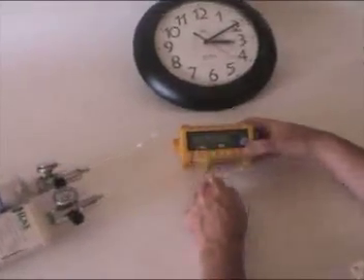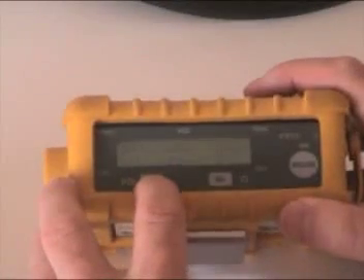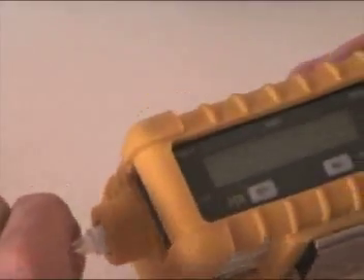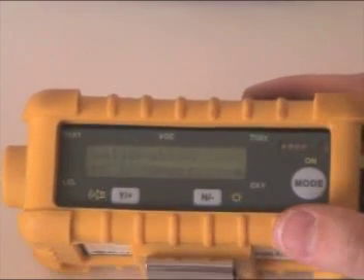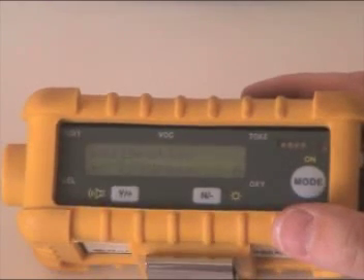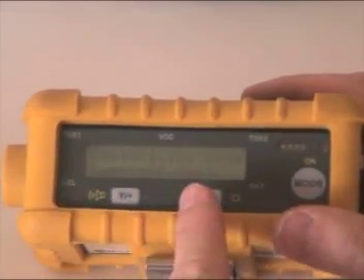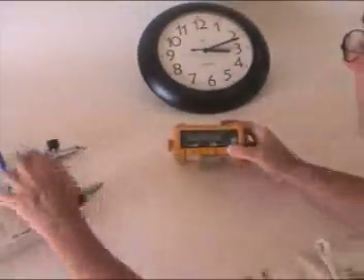Single sensor calibration — we'll get right to that. We're going to say yes. Now we have to pick. With the mode button we go over one to VOC and say yes. Apply gas — turn on the knob, attach the luer fitting. Calibration in progress; once again this takes about a minute. VOC cal tells us the reading is 100. Now we're going to turn off the calibration gas — remove the connector, turn off the gas. We could go on and calibrate another sensor, but we're going to say no.